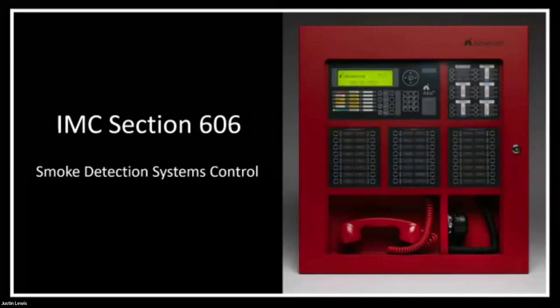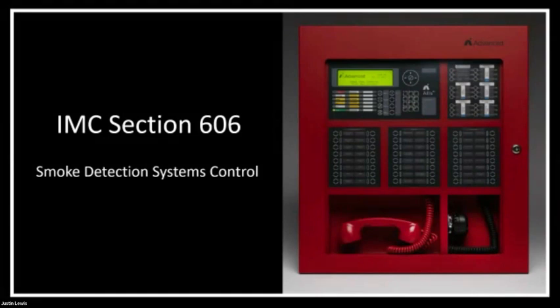The International Mechanical Code states that smoke detectors are required in systems, quote, with a design capacity greater than 2,000 CFM. Now, there's a lot of other caveats, there's deviations, and there's other requirements, but this specifically is one that we run into quite a bit. The verbiage of greater than 2,000 CFM can really be a gray area when specifying whether or not a system requires a duct detector.